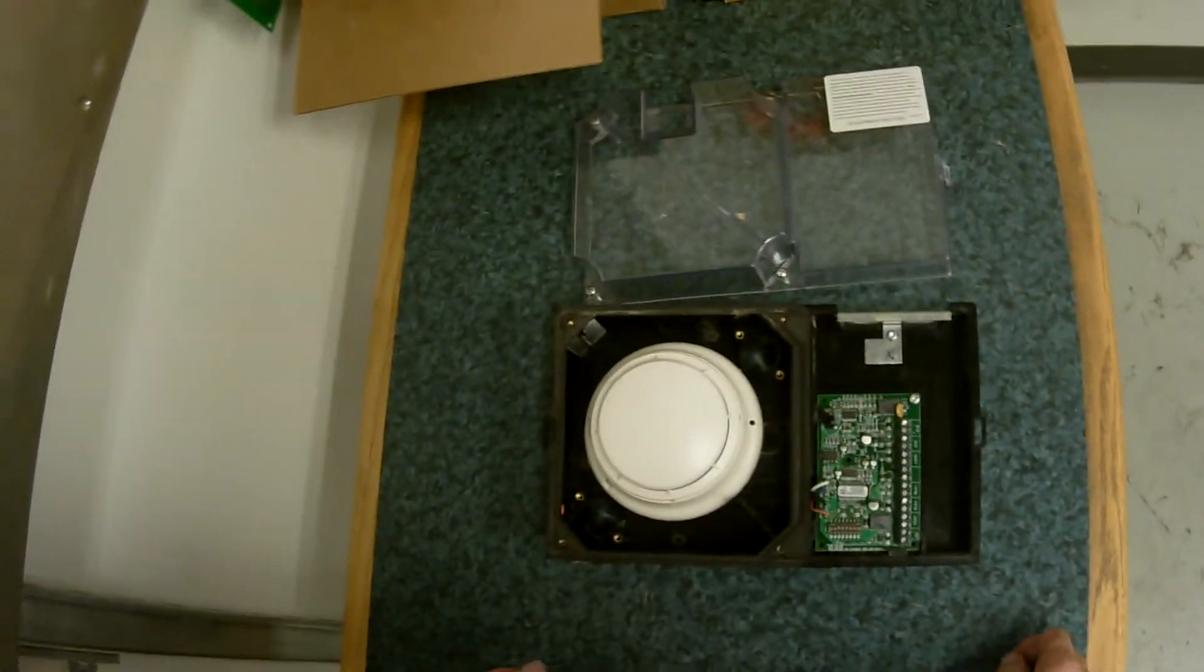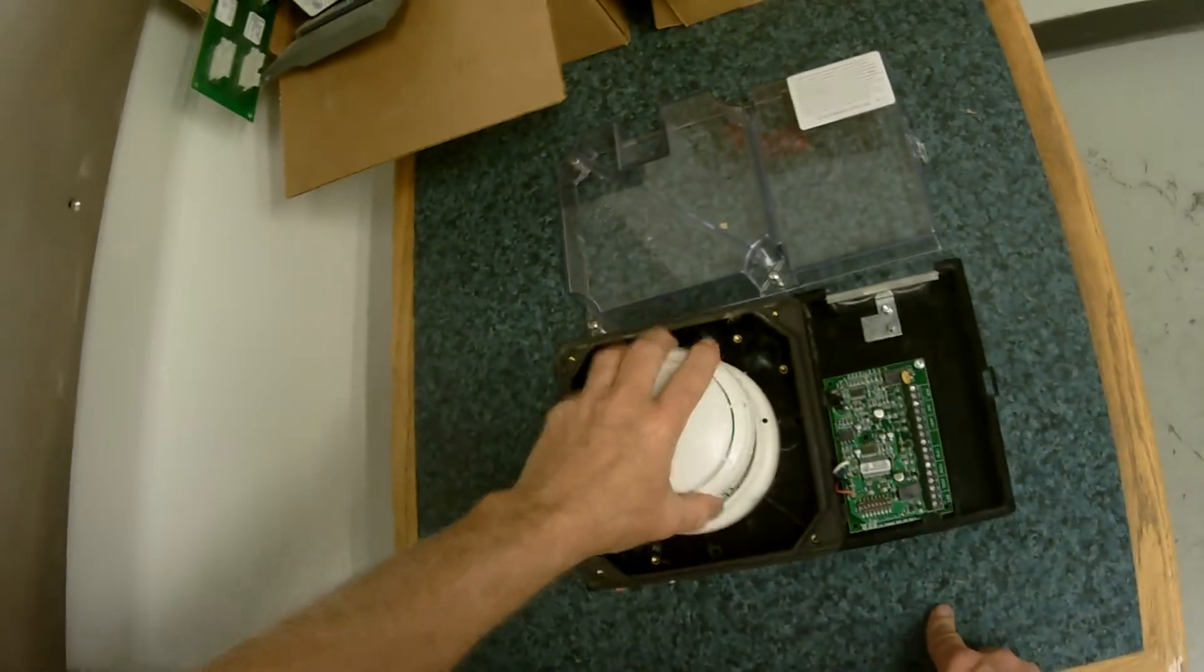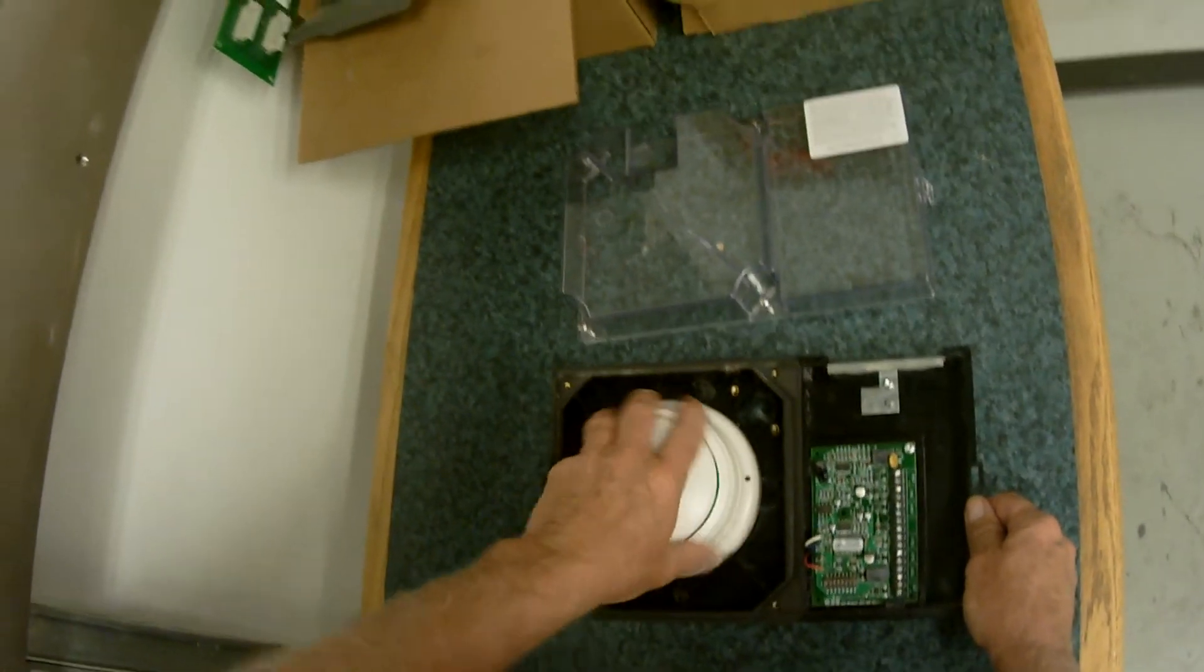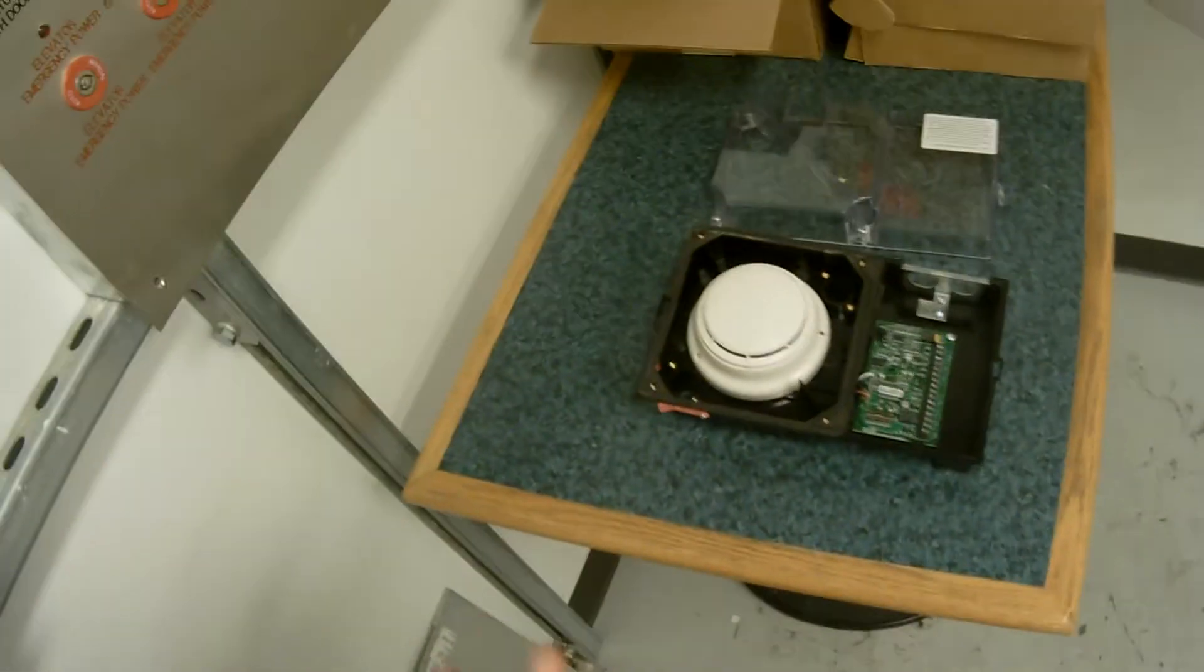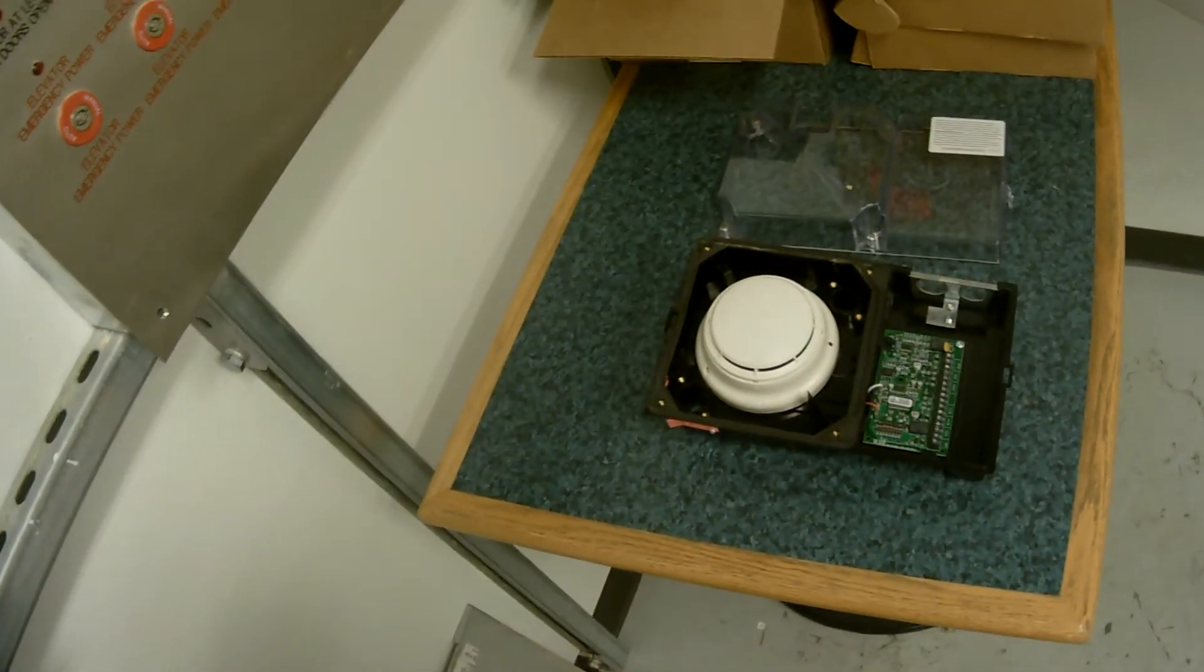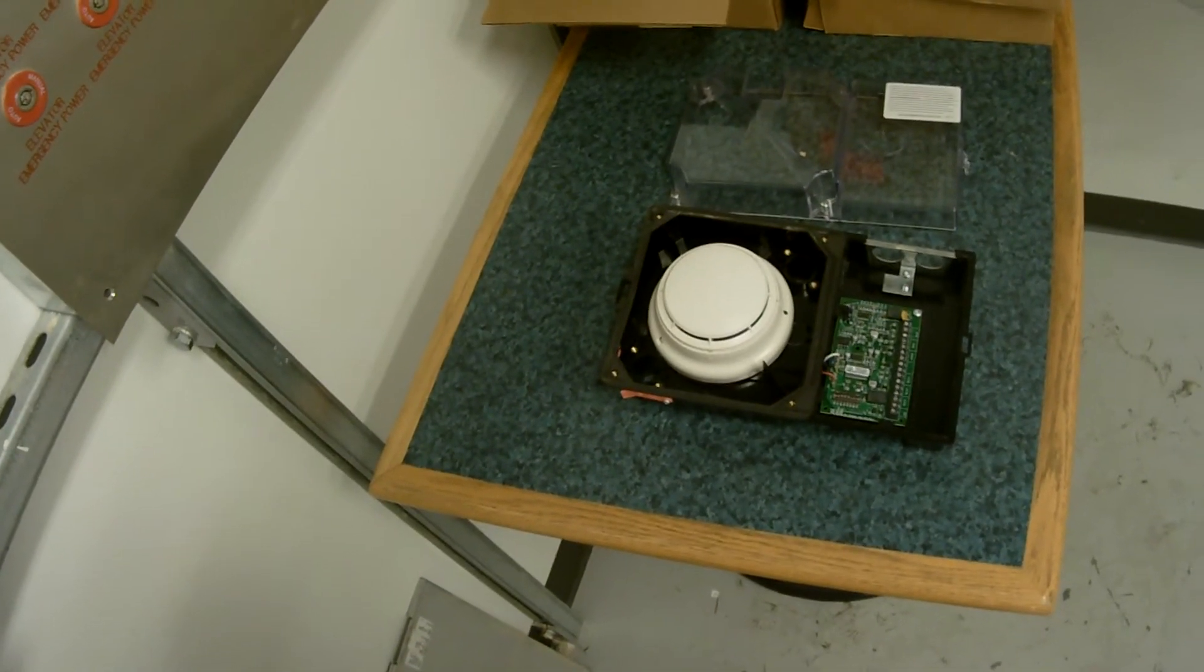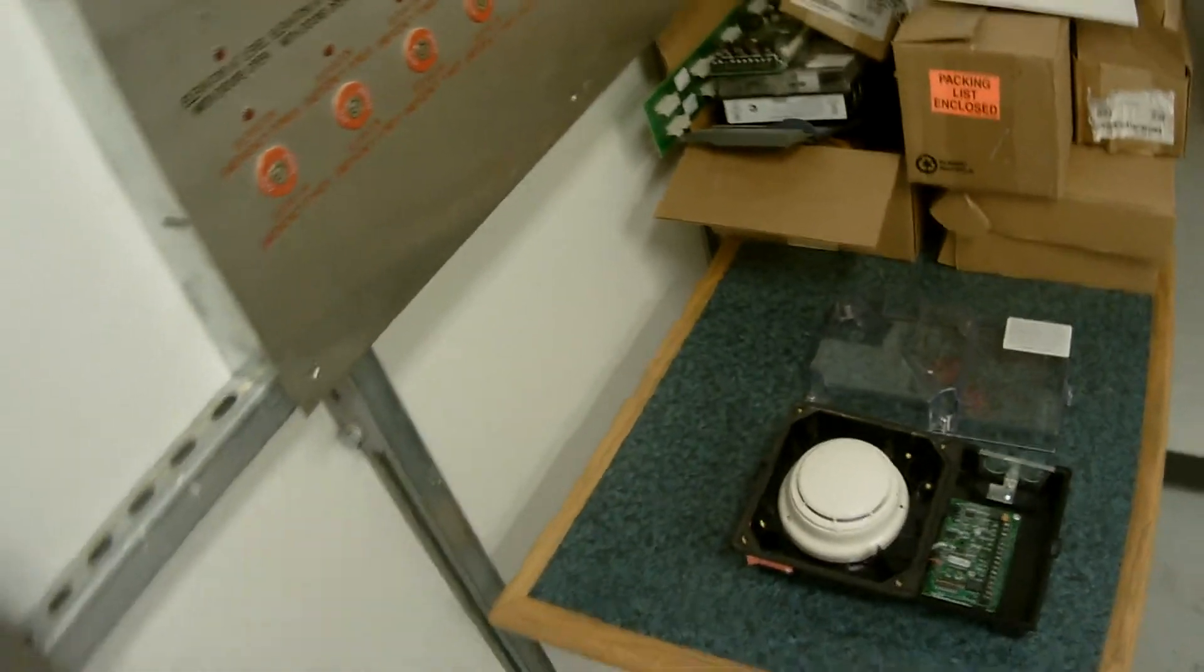I could replace the board, I replaced the head - anything that's left is a bunch of plastic. There's nothing else that can go wrong with this. I've argued this point before, but I had to look into this a little further because I did exactly what the customer said and replaced the whole duct detector and it cured the problem.